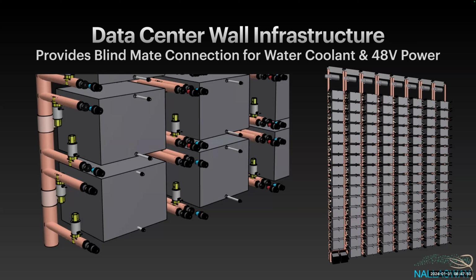So the PCB is going to have the 48 to whatever. Yes, the PCB has the 48 down, either with two steps down to half a volt, or even people are doing it in one step now. And we'd also have bus bars running down the 48 volt as well, so you'd have redundancy between these power supplies. If one failed, the others could step in to power the module. So we're thinking along those lines.